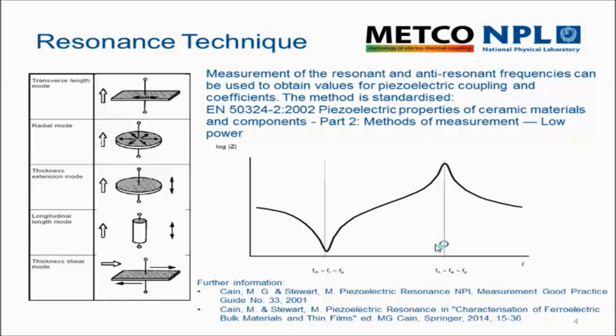This resonance technique is nothing new — it's been around a long time, and it's encapsulated in a European standard, EN50324. This is a systematic method for evaluating piezoelectric coefficients from the resonance spectrum. A typical sample will have many different resonant frequencies and different resonance modes, and if they're all close together they influence each other, and we don't get a clear resonance–anti-resonance spectrum, which has an influence on the results.